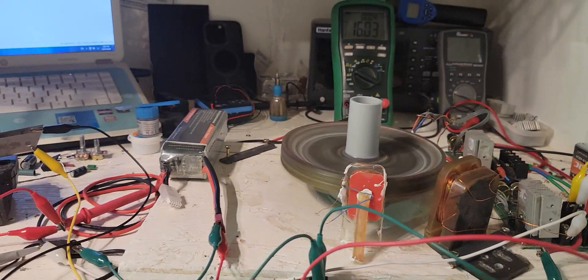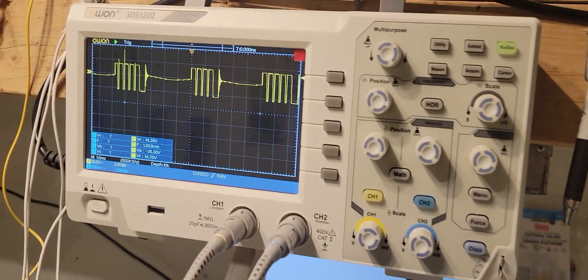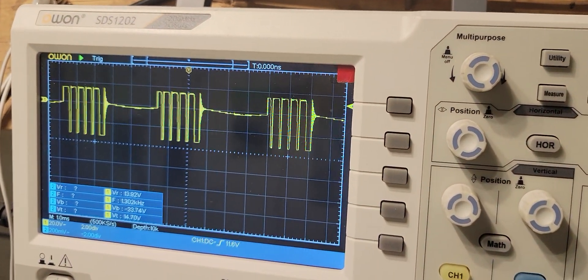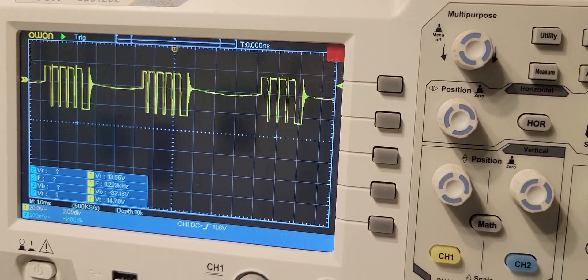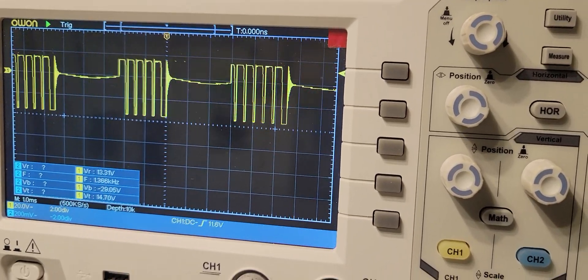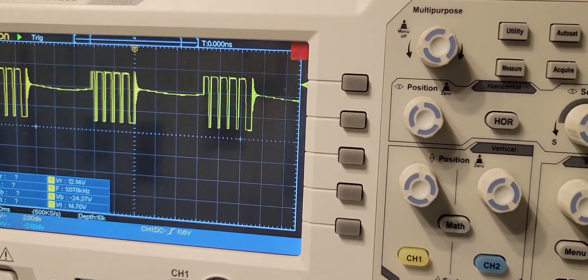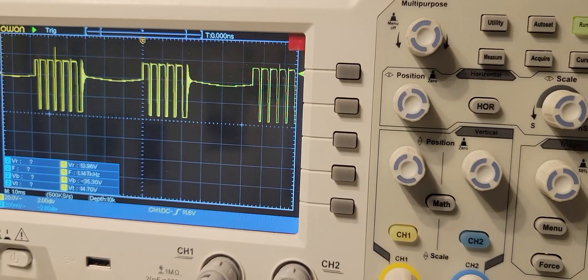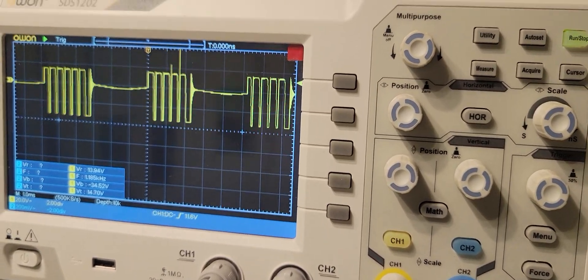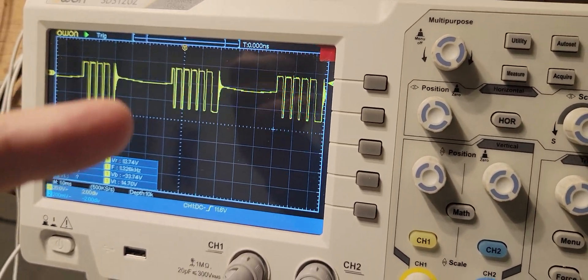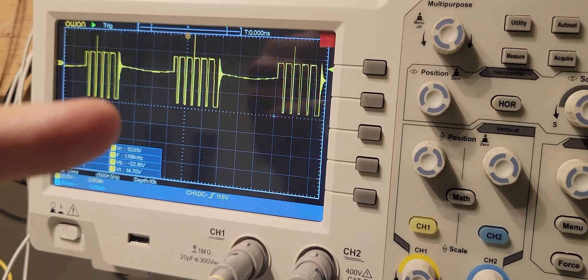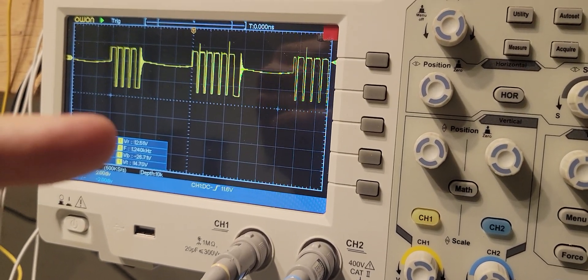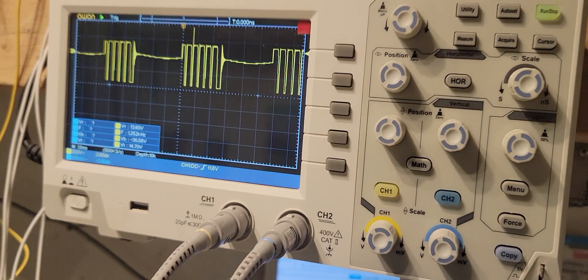It is nice to have it at these higher voltages because it's watts you're converting. You're making watts out of those higher volts, right? It's potential. But you don't want to go too far because as you get further down the scale, it slows down on how much you're actually putting into the caps. So you've got to really tune it to the motor you're using.